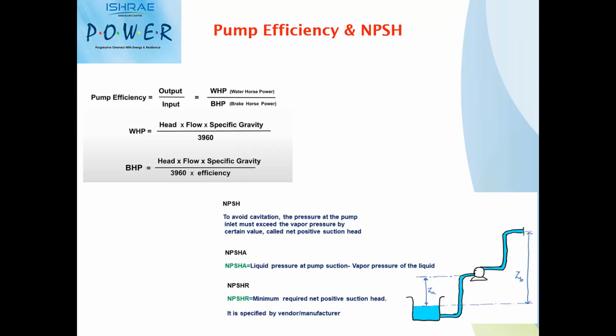One more terminology which is very important for our HVAC industry is the net positive suction head required by the pumps. So what is NPSH basically? The NPSH value is basically the pressure or the suction pressure required by the pump to operate without any cavitation. One thing I want to emphasize is that all the pumps used in our HVAC industry are non-self-priming pumps. Pumps cannot suck the water. This is a typical sketch I have shown, but pumps cannot suck the water from a lower level than the pump. We should have a positive suction on the suction side of the pump to have smooth operation of the pumps. All the pumps we are using in our HVAC industry are non-self-priming pumps.